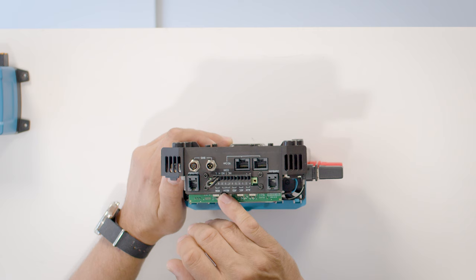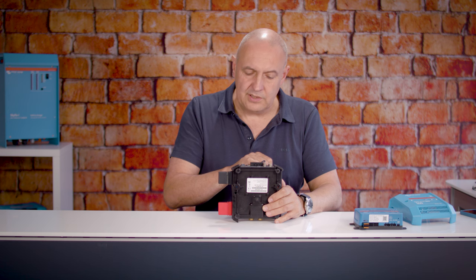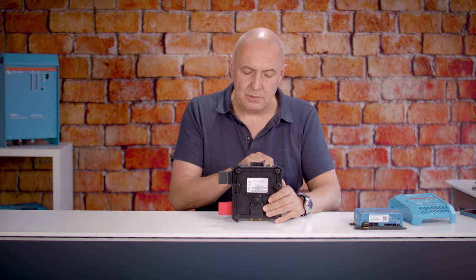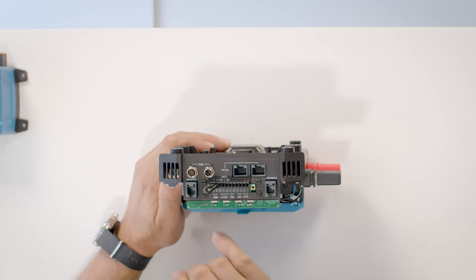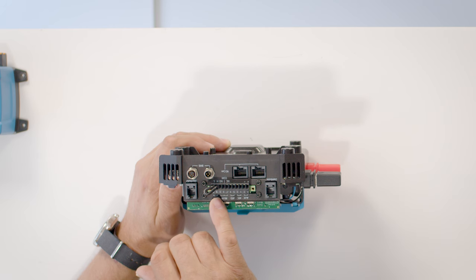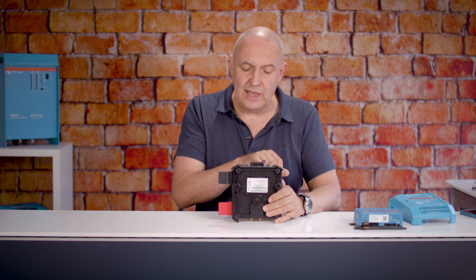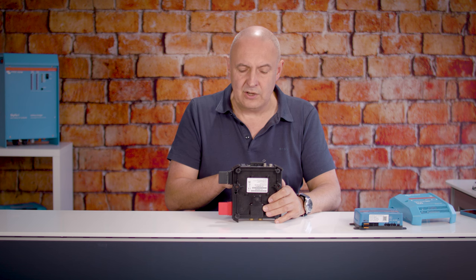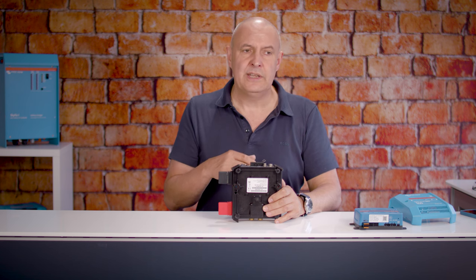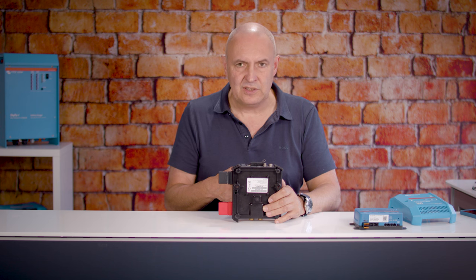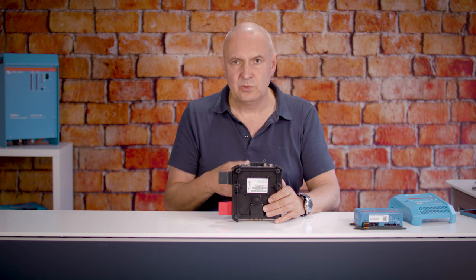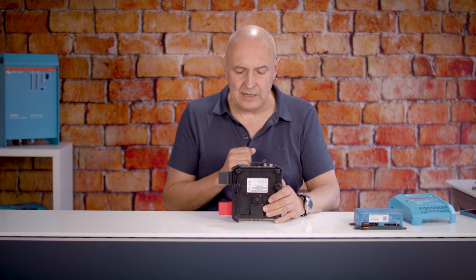We have a programmable relay, and with this programmable relay, you get given access to both the normally closed and the normally open contacts. And this can be configured using the VictronConnect app. Finally, you'll see that there's a link wire provided across terminals 10 and 11 by default from the factory. This link wire can be replaced with a remote switch, and this will then allow you to open and close the main contactor manually to provide a manual battery isolator switch for the system, as well as its use as an automatic one based on the battery condition.